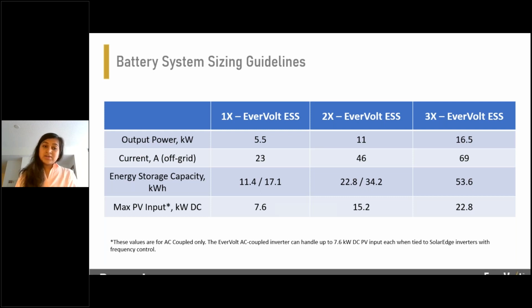One thing to keep in mind is the maximum PV input as well. Because during an outage there is no grid interconnection, it is important to keep the size of the PV input connected to the battery in check. If the battery is fully charged and there are not enough home loads being powered, then the PV would shut down. So the maximum recommended size of PV for a single system is 7.6 kilowatts with AC coupled. And the 7.6 is usually achieved with SolarEdge inverters and frequency control. So that's where these sizing restrictions come into play.